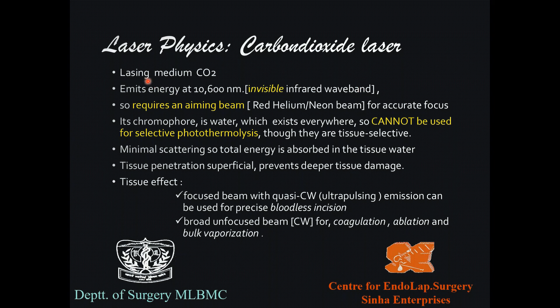The carbon dioxide laser uses CO₂ as the lasing medium in the invisible infrared waveband and requires an aiming beam — supplied by a red helium-neon beam. Its chromophore is water, which is omnipresent throughout the body. The chromophore is the material present endogenously or introduced exogenously that absorbs the particular wavelength; without absorption, the laser can give no effect. Because water is everywhere, the CO₂ laser cannot be used for selective photothermolysis.